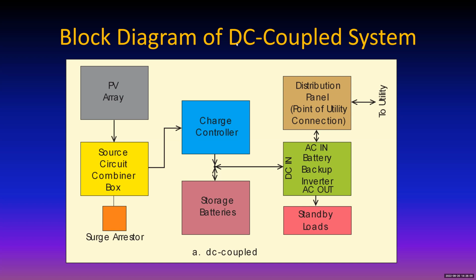And unless you do sufficient filtering on your sine wave in your green box, battery backup inverter, or any inverter that's connected to the grid, you can't sell it. You can't list it to 1741. And the utility doesn't have any interest at all in buying it from you. So there are lots of harmonics, but second and fifth in particular are filtered out by electronic filters within the inverter.